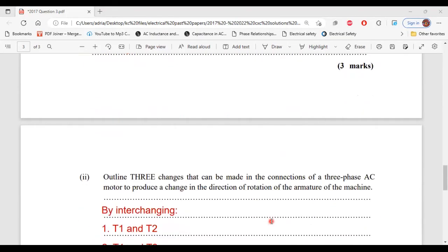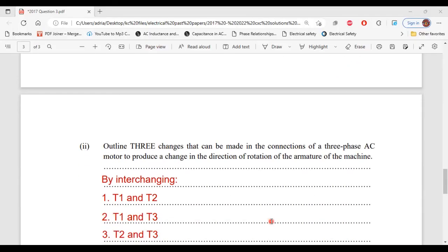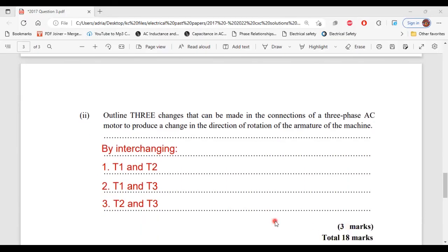Part two says, outline three changes that can be made in the connections of a three-phase AC motor to produce a change in direction of rotation of the armature of the machine. The change in direction of rotation of the armature can be done by interchanging T1 and T2, or T1 and T3, or T2 and T3. That's it for part two, and that's it for this question.